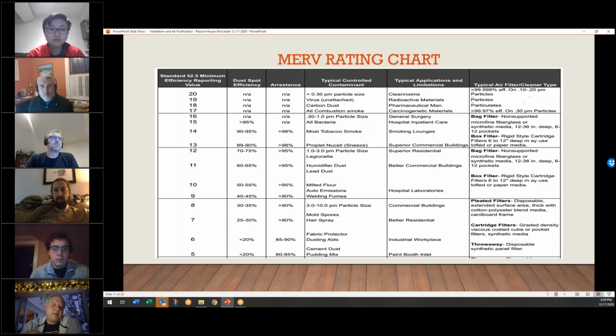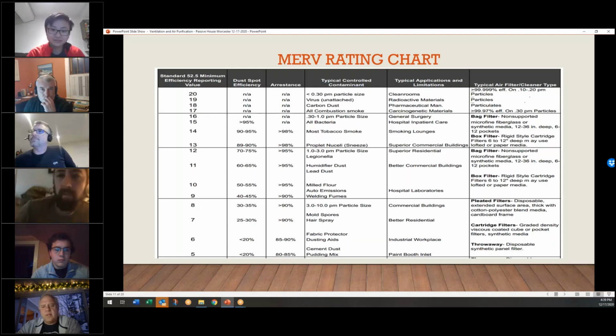And then again, you can get all the way to 16 as a cartridge type filter, and above that you move into the HEPA range, where you're at a MERV of 20. And then there are even ULPA filters, which are very rarely used, but they're used in really high level clean rooms and such, where they need really tight filtration. So that's the basics of the filters there. And we can go to the next slide.